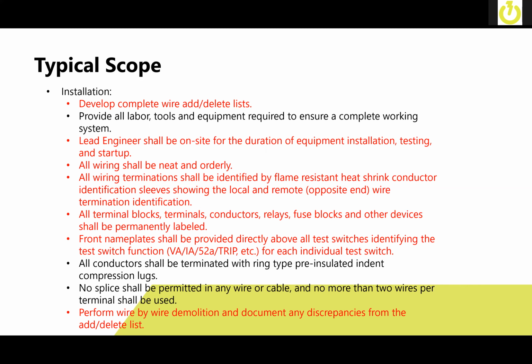Wiring terminations get identified by a flame-resistant heat shrink conductor identification sleeve showing the local and remote opposite end. What that allows you to do is quickly and easily troubleshoot without having to pull out the drawings. You can look at the wire label and see exactly what it's supposed to be landed on, and then you can see exactly where it's supposed to go. So if you're trying to troubleshoot, you don't have to pull out the drawings and start trying to figure it out. You can look at the label and immediately put your meter on where it needs to go.